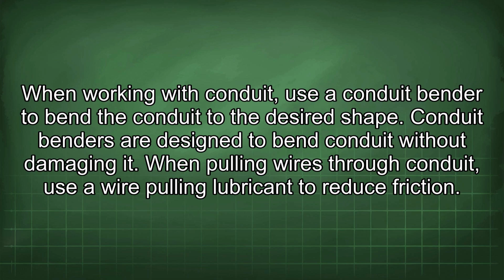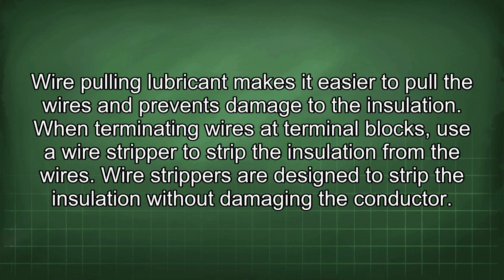When working with conduit, use a conduit bender to bend the conduit to the desired shape. Conduit benders are designed to bend conduit without damaging it. When pulling wires through conduit, use a wire pulling lubricant to reduce friction. Wire pulling lubricant makes it easier to pull the wires and prevents damage to the insulation.